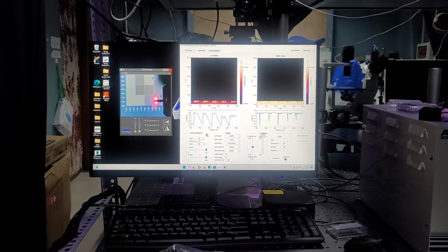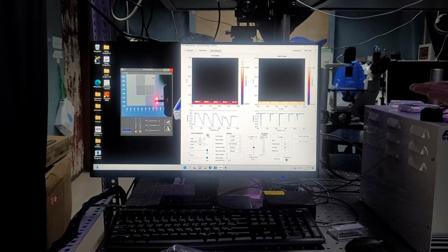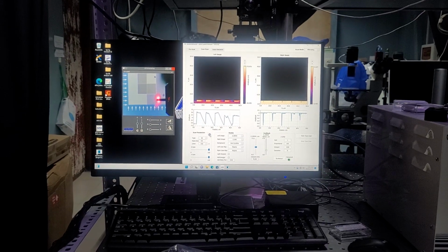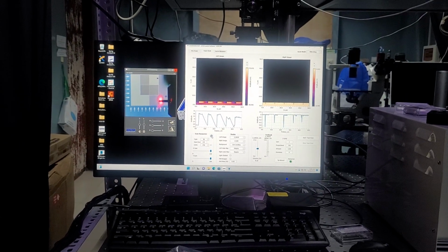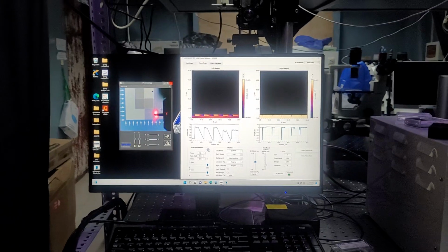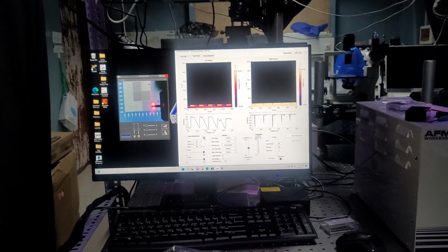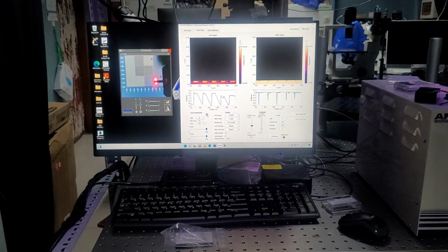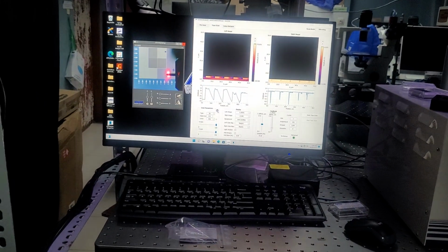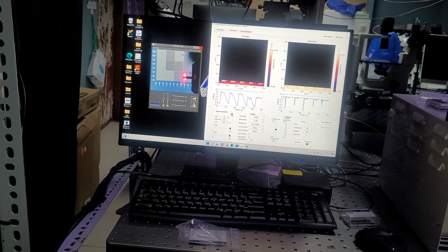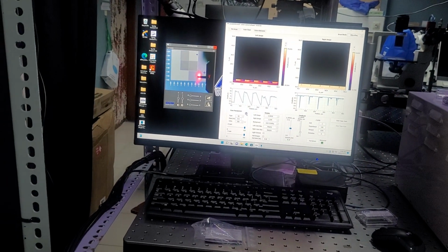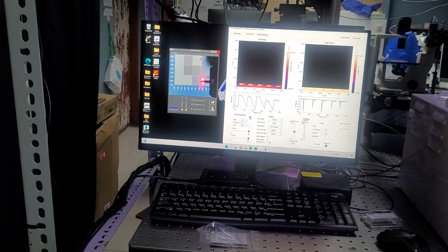And if you're trying to use it to analyze something like this, those curves can be very problematic. So those strain gauges are mounted on the X and Y piezos in order to force them to be linear, to where 1 volt is 1 micron, 2 volts is 2 microns. And it does this at the expense of some noise.